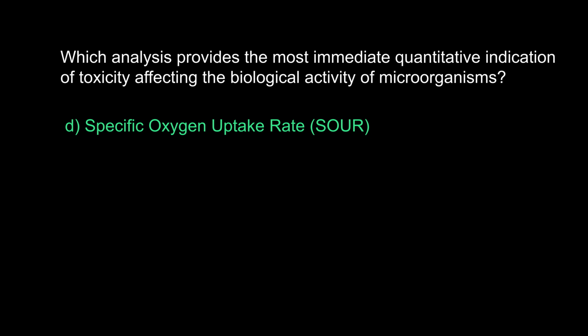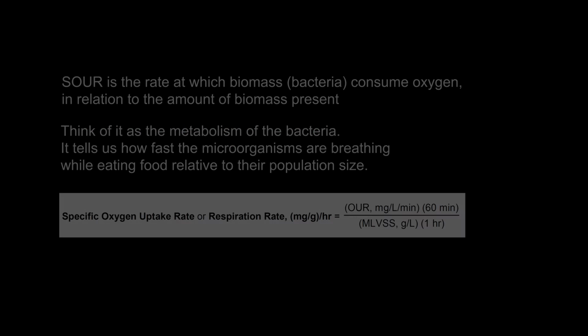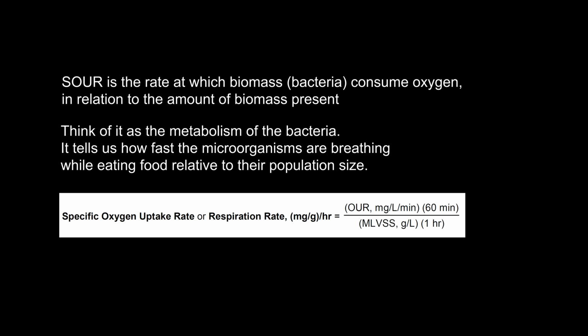The answer is D. Specific oxygen uptake rate. One of the best techniques for detecting and tracking your plant's performance during a toxic event or overloading of nutrients would be to perform a SOUR test, which stands for Specific Oxygen Uptake Rate. This test measures the actual metabolic rate of your microorganisms, which is like the breathing rate of your bugs.